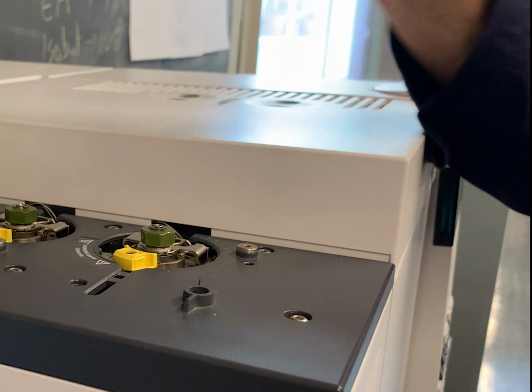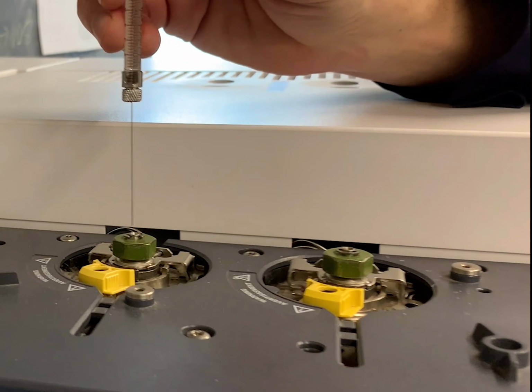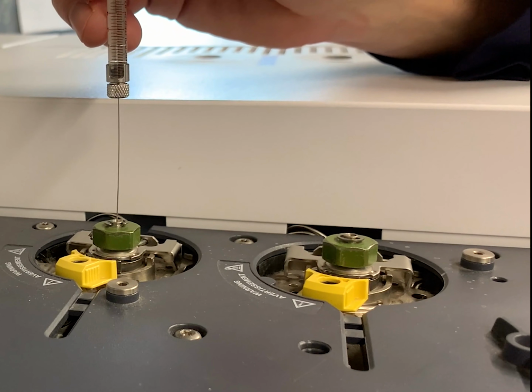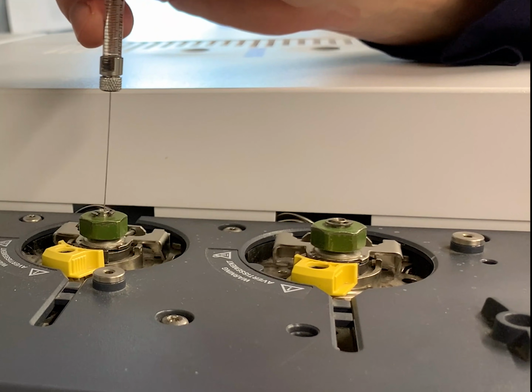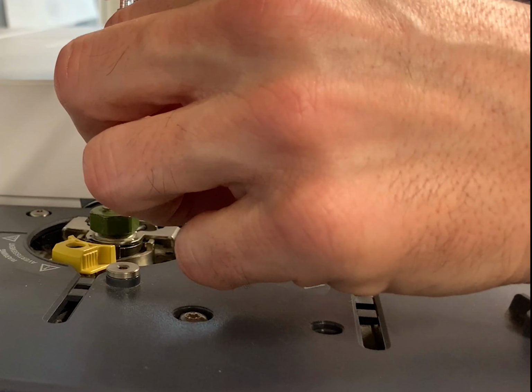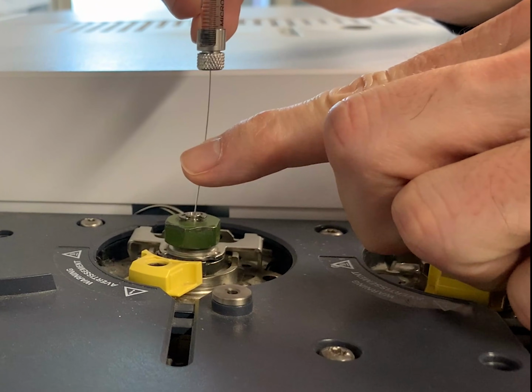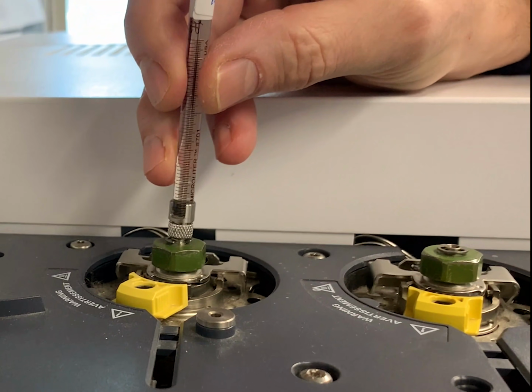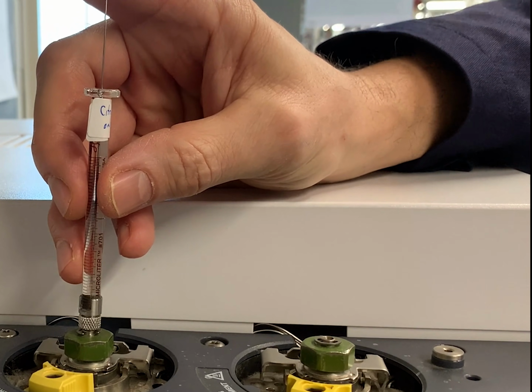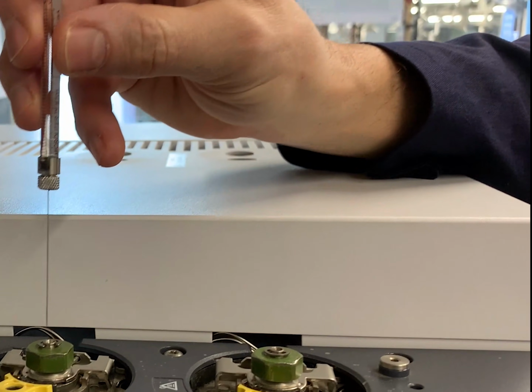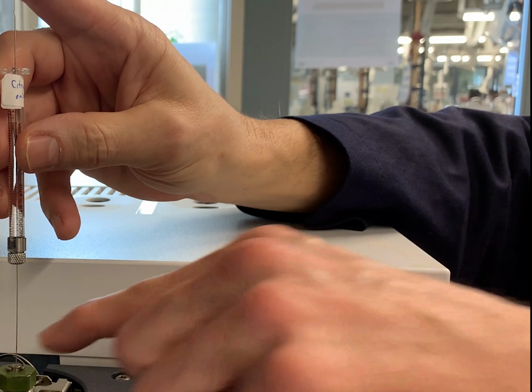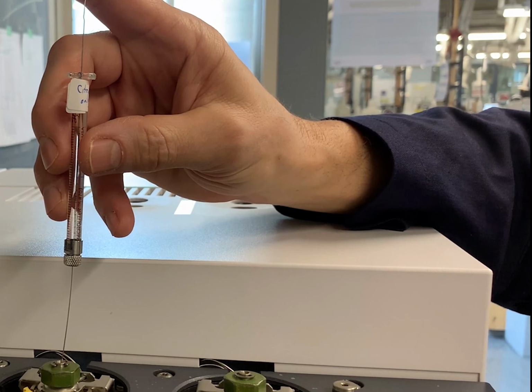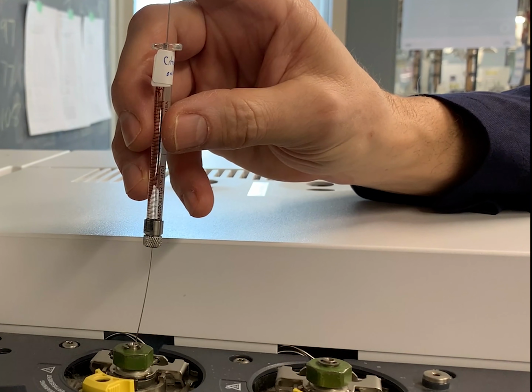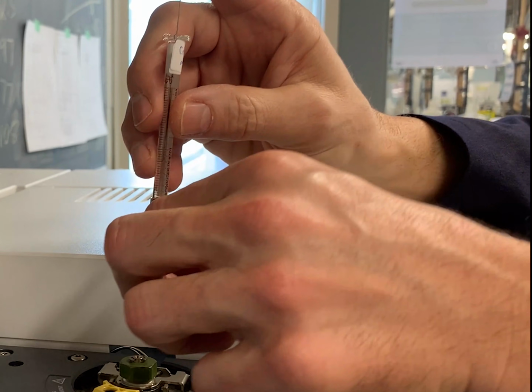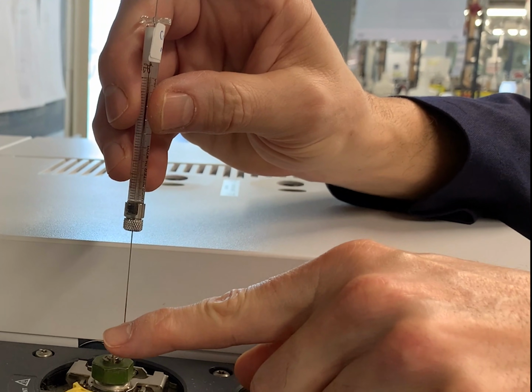And then on the GC itself, one of the most common issues is right here. You take too long to push that plunger down, or you bend it. The way to avoid bending it: guide it into place, and then push it straight down, and then you can do your injection, and then you push start. By holding it in place right here, you're heating up this area, you're heating up your sample, and giving it a chance to start to vaporize, and that's why you'll get bad peaks. So nice, smooth injection. Here, I'll just put my finger there to show you.